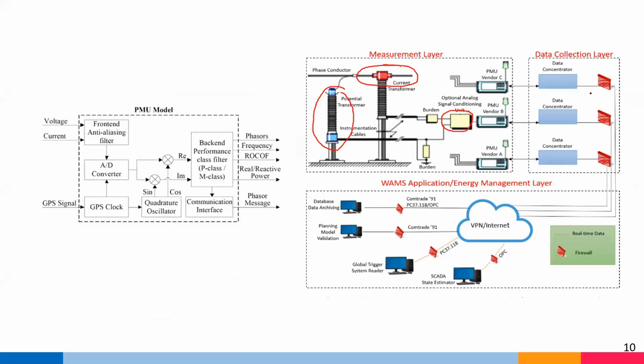At the control center, we have devices which align this phasor information from different locations in the grid with respect to a common time frame. Because GPS is available to all, we can have a storage system where this GPS signal also comes, and it will align whatever data is coming from the field with respect to that GPS signal. There will be a time stamp with each phasor, and a time stamp at the control center storage as well.